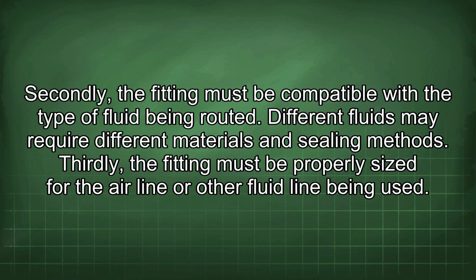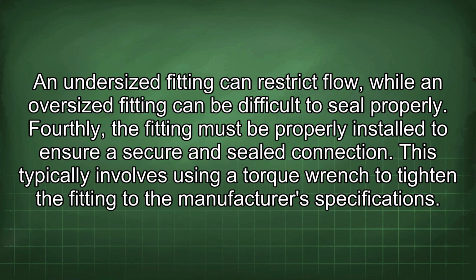Thirdly, the fitting must be properly sized for the air line or other fluid line being used. An undersized fitting can restrict flow, while an oversized fitting can be difficult to seal properly. Fourthly, the fitting must be properly installed to ensure a secure and sealed connection. This typically involves using a torque wrench to tighten the fitting to the manufacturer's specifications.